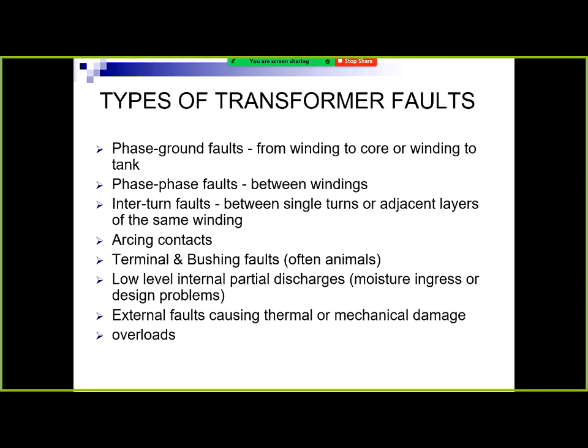What they didn't want was, we had an outage of a transformer, we damage another transformer that just has a fault on it, and then we damage another transformer, so we've got 2 transformers which are damaged and just 1 transformer. They can take a year to replace transformers if you don't have a spare. They take a really long time to order and get. Pay a bit extra and you might get it for 9 months, but they're long lead items, transformers to buy. That's probably the big concern, was something like that. So overload's not really an issue for us because if it overloads, we trip. It's basically what we've got on it, and at sites which only have 2 transformers, one of those transformers can take the full load, so we don't have an issue.